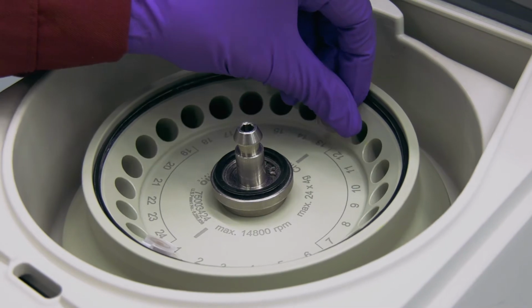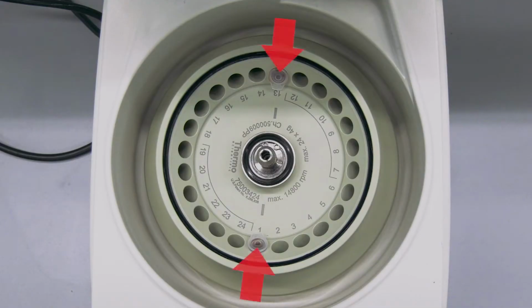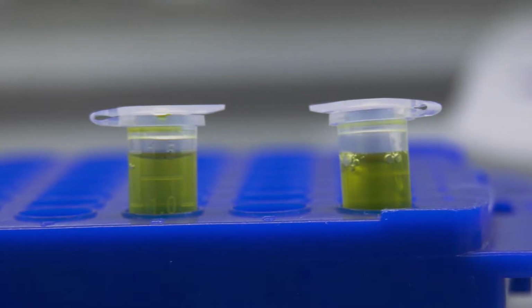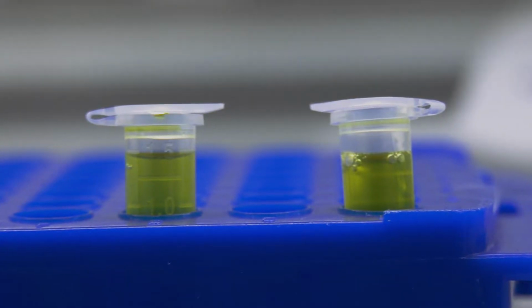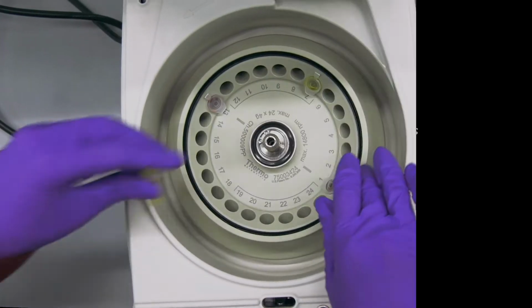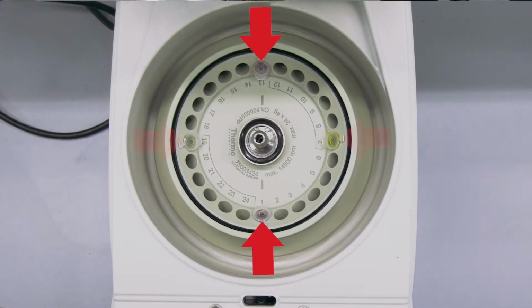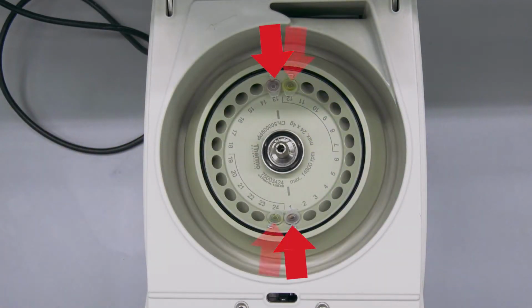The rotor is now balanced. Centrifuges should only be operated when balanced, and each sample should also have a similar volume of liquid to aid in balancing. Bear in mind the tolerance on differing volumes decreases with increasing centrifuge speeds. If you need to add more samples, remember to add them in pairs that are opposite each other to ensure the machine is balanced.